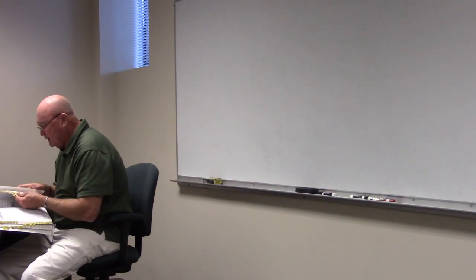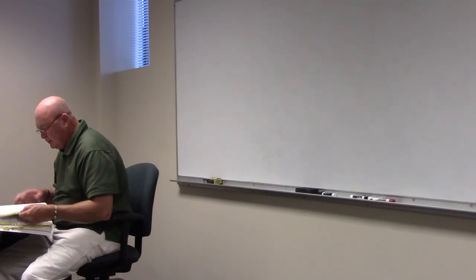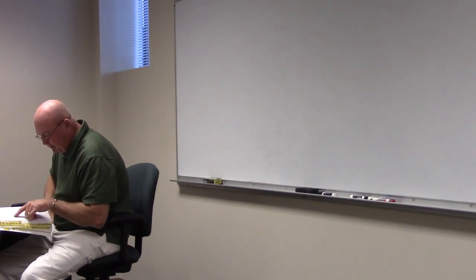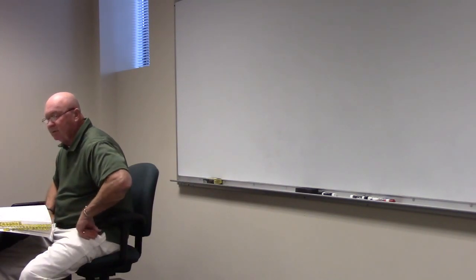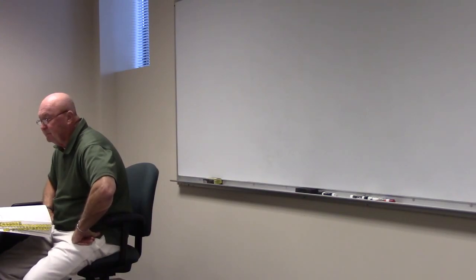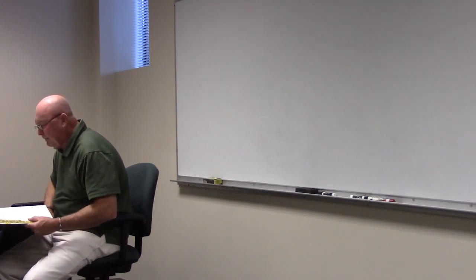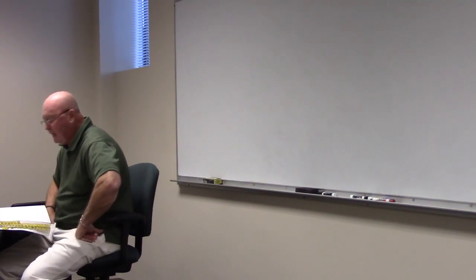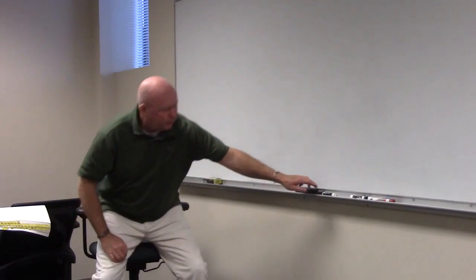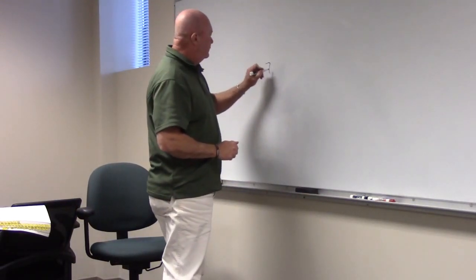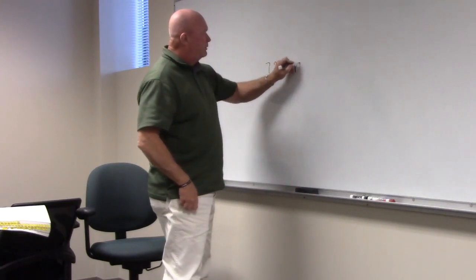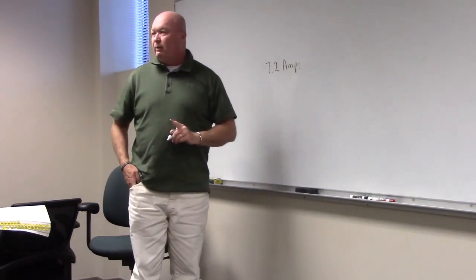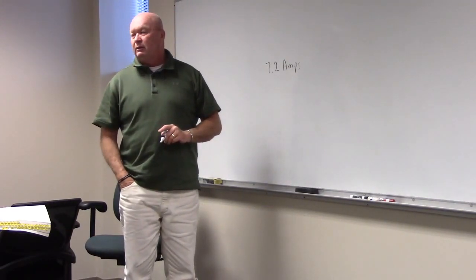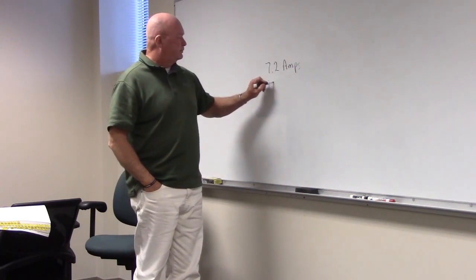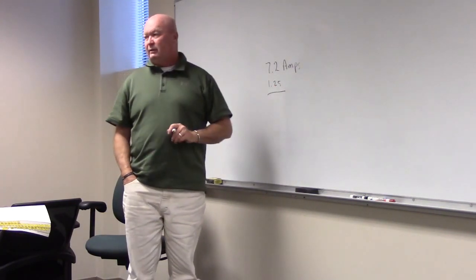And we're going to look up the rating of this motor. Somebody tell me the 115 volt third horsepower motor, how many amps would it be? Should be 7.2. Yeah, 7.2. Now what are we going to do with that 7.2? Motor, well pump, what kind of load? Continuous? Continuous.